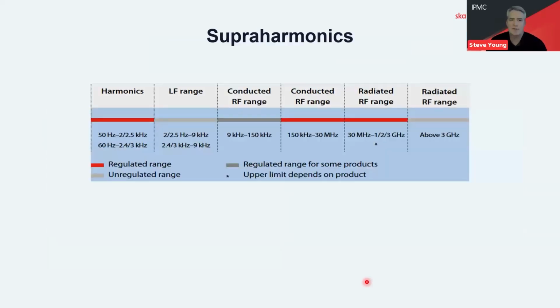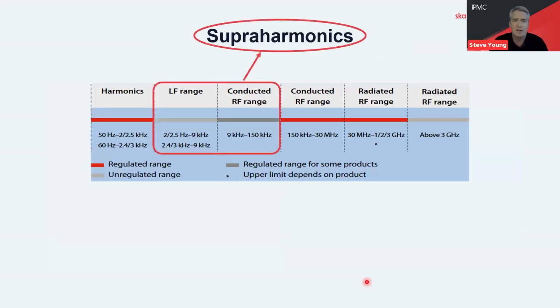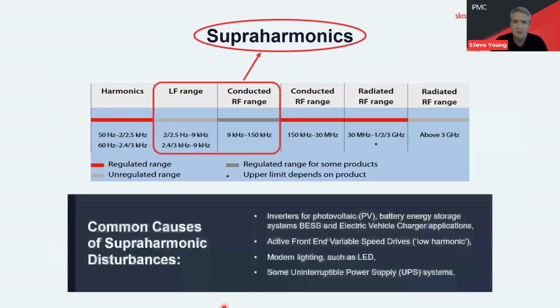So on a wider range of frequencies, if we consider harmonics being at the lower end of that, and electromagnetic fields and EMC being at the higher end of that, there's traditionally been a gap in the middle, which is now commonly and affectionately known as superharmonics. So if we look at the different types of supraharmonic generating items of plant and equipment, perhaps the most common one that I see are inverters that are on modern PV or photovoltaic farms.